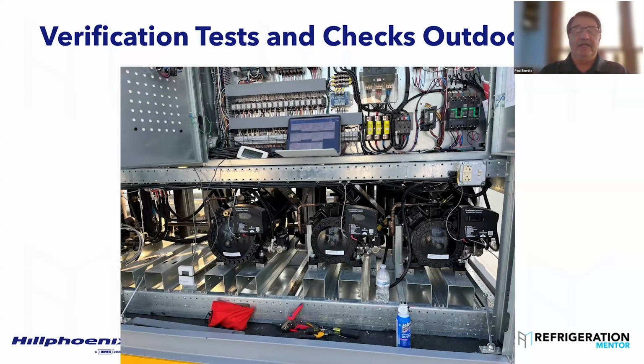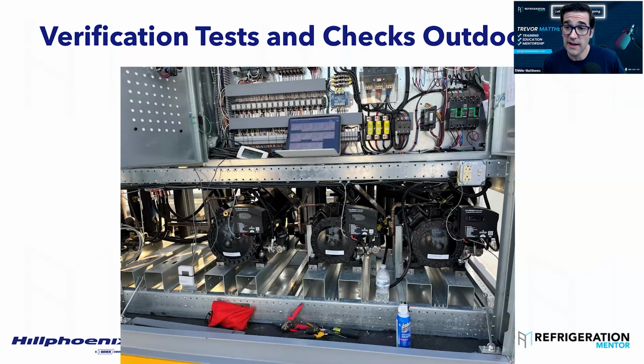Exactly. And in your case, you guys are popping off relief valves and blanking them off to be able to do that. Yeah, so you've got to blank off the compressors, you've got to blank off the pressure reliefs and pressure test that way and hold it for over 24 hours.